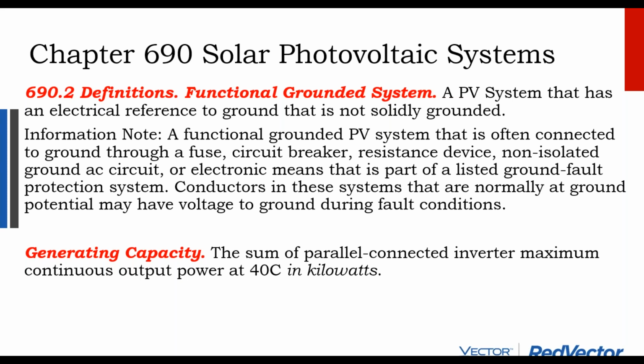Generating capacity. So this is kind of interesting. The generating capacity is the inverter output in kilowatts. So on your interconnection agreements, it says the size of the system. The traditional, if you're asked on a permit document, what is the system size, and it's not telling you specifically if it's referring to the size of the DC input or the size of the AC output, the generating capacity is based off the AC output.